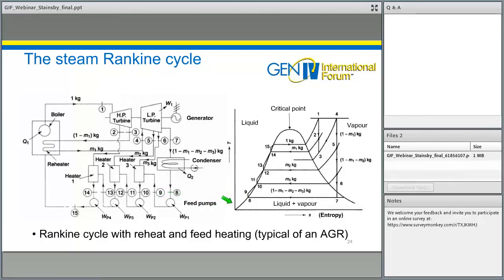And then we go up through these various pumping and heating stages. So the first feed pump takes us up to there, the first feed heater takes us to there, the second feed pump to there, and so on, until finally we reach the end of the feed chain where the water is almost at boiling point. It's hot water, which is only a few degrees below the boiling point. So all the boiler is doing really is it's not really raising the temperature of the water at this stage. It's actually changing its phase because it's already almost at boiling point.